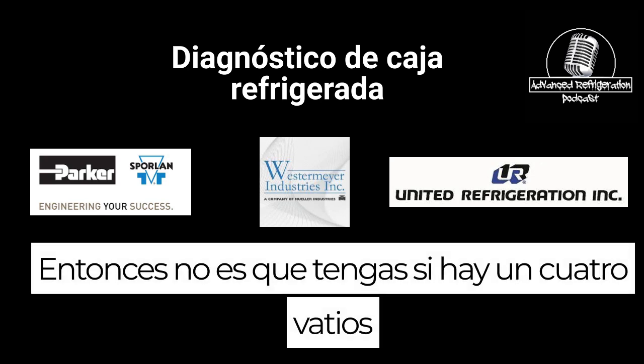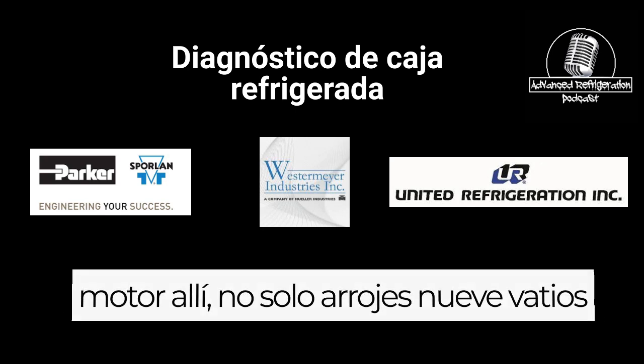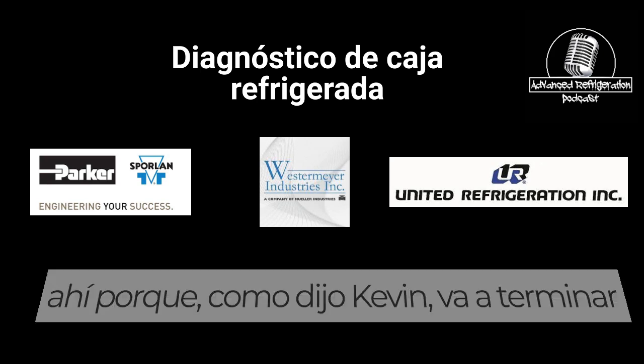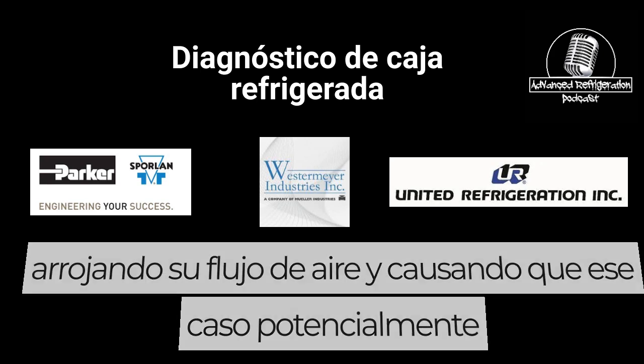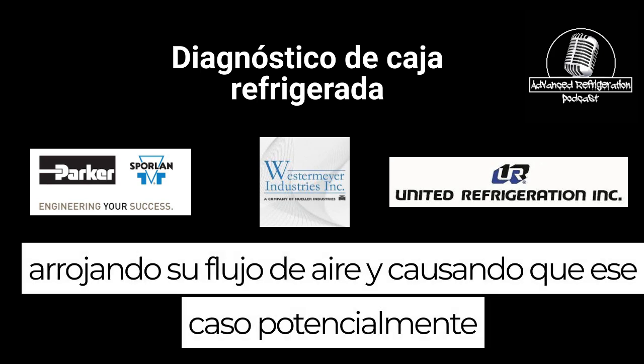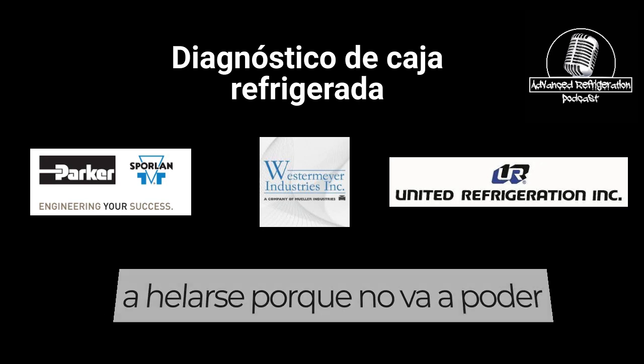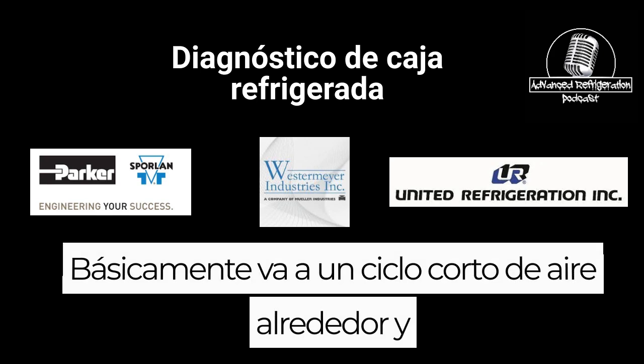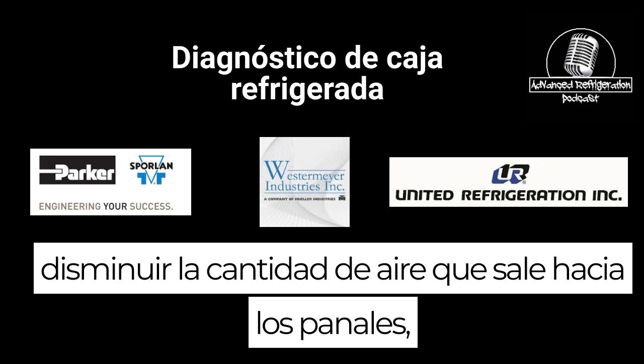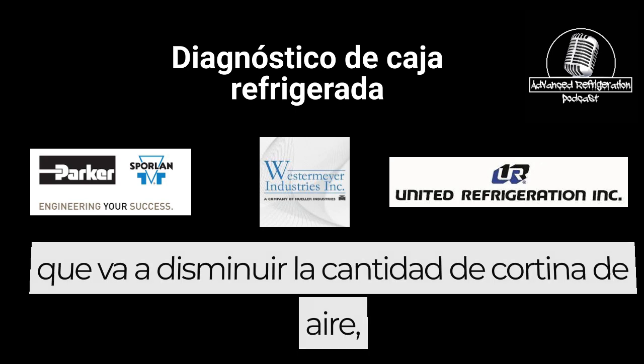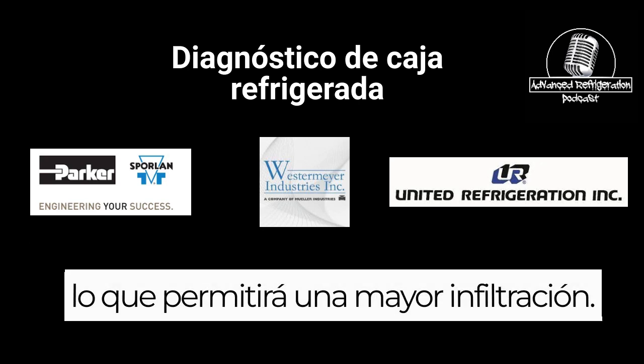So if there's a 4-watt motor in there, don't just throw a 9-watt in there, because like Kevin said, it's going to end up throwing off your airflow and causing that case potentially to ice up, because it's not going to be able to push that airflow all the way around. It's basically going to short cycle that air around and lessen the amount of air going out towards the honeycombs, which is going to lessen the amount of air curtain, which is going to allow for more infiltration.